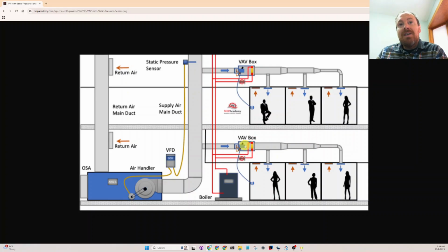So this should be an air damper position on the VAV system. The algorithm in the real world would look at all these different air dampers, and then we would filter for the maximum values that we're looking for in the algorithm. And then also in the ping-pong algorithm, we demonstrate the basic concepts of how to reset a static pressure reset, for example. We're actually resetting between minimum and maximum values of how the fan on the air handling unit system would control to a duct static pressure.